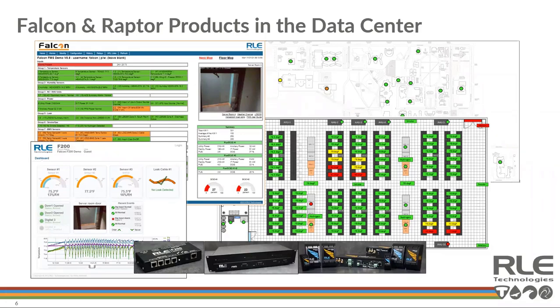I see a lot of customers who have nothing on site except a number of sensors and local alarms. Now they're looking to incorporate a DCIM, data center infrastructure management system, or something a little more comprehensive, but the budget doesn't allow it. The nice thing with a Falcon FMS is they can aggregate all those different sensors and signals. It's very scalable in that sense. Then, as their budget allows, we can push that information out via SNMP, Modbus, or BACnet protocols and integrate it into a management system very easily. So now it becomes middleware, where it was kind of the front end, just aggregating all those different sensors and equipment. The scalability from 8 to 104 inputs, just by adding expansion cards, is not something a lot of products give you within a single device.